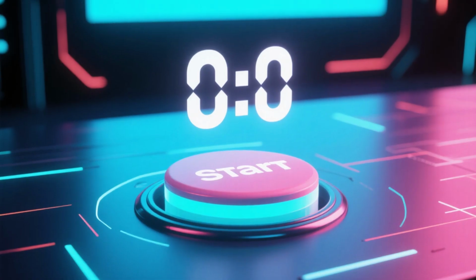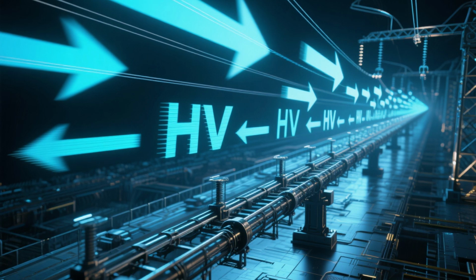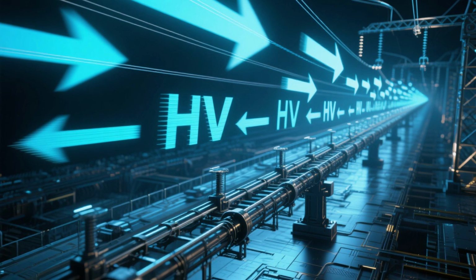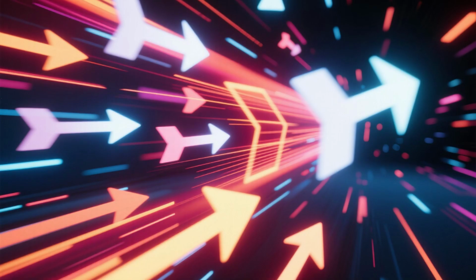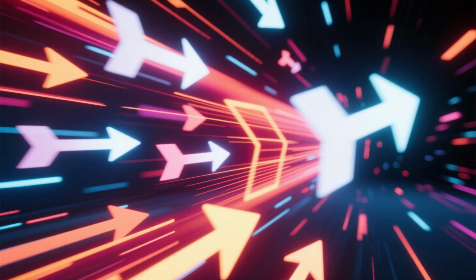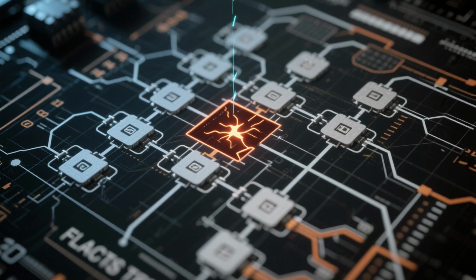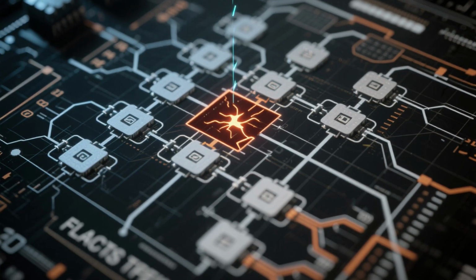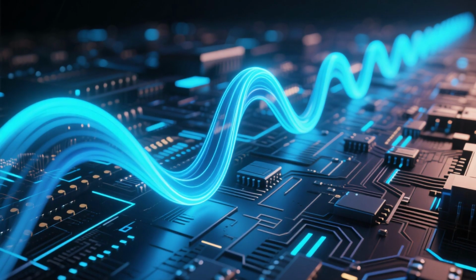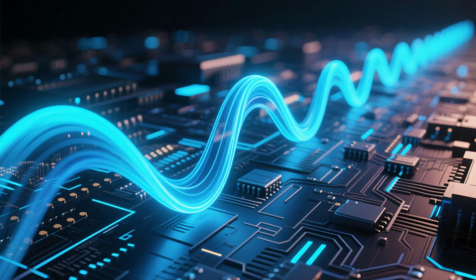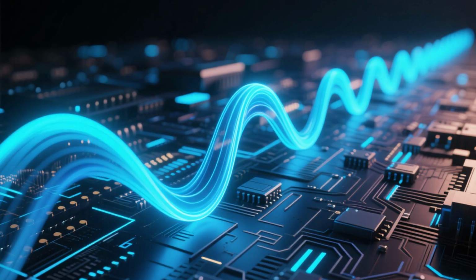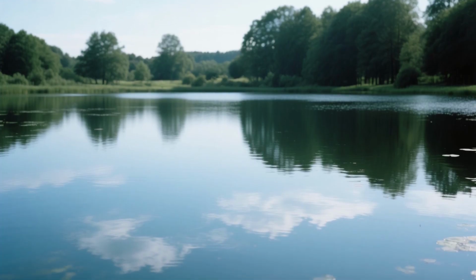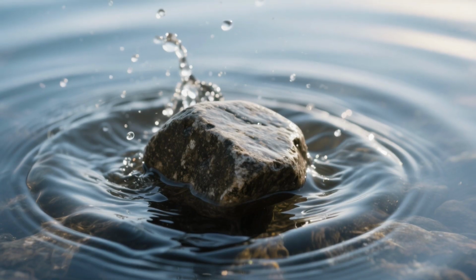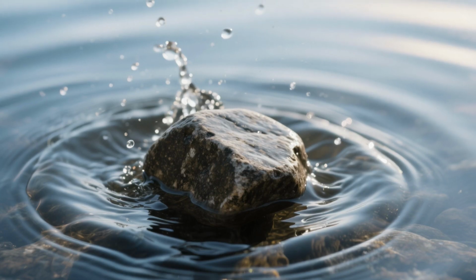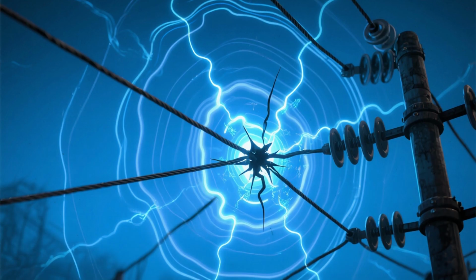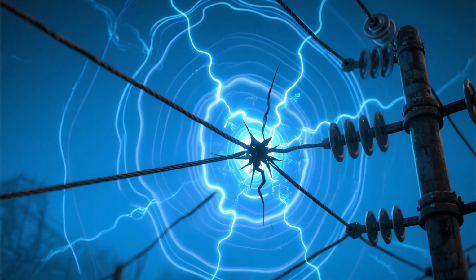So let's get started. When a fault occurs on an HVDC line, the first few milliseconds are critical. Primary protection schemes are all about speed. The goal is to detect and isolate a fault before it can destabilize the entire system. One of the most effective and widely used primary protection methods is based on traveling waves. Imagine a calm pond. If you drop a stone into it, ripples or waves travel outwards from the point of impact. A fault on a transmission line creates a similar effect.